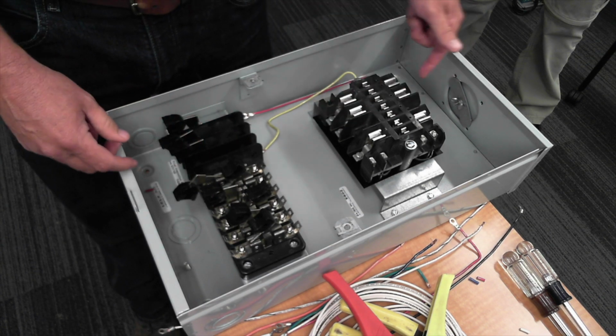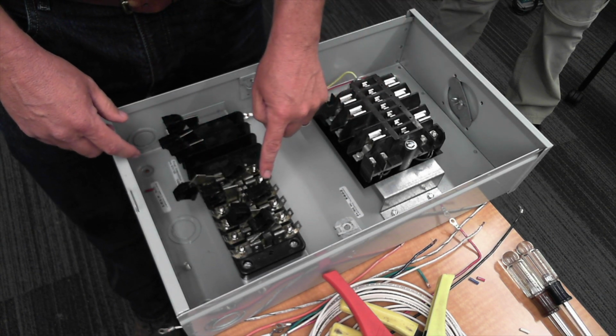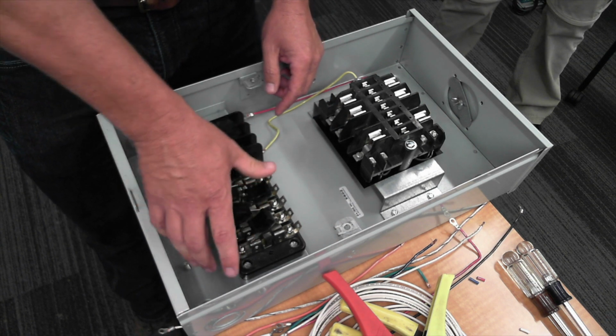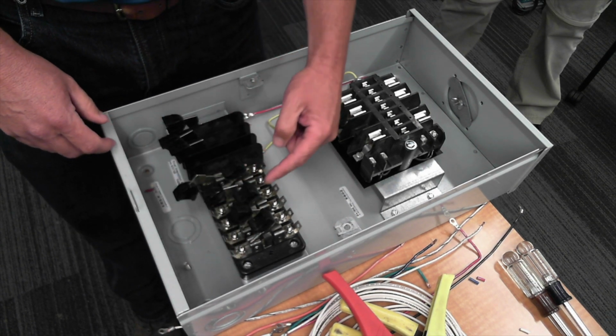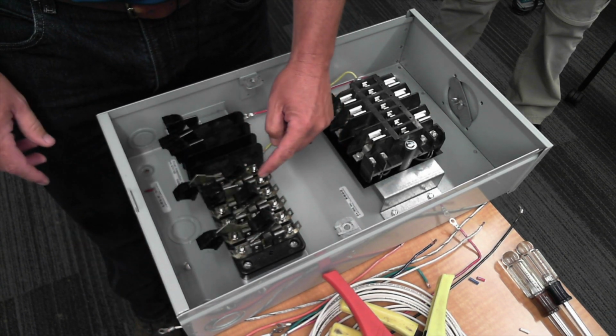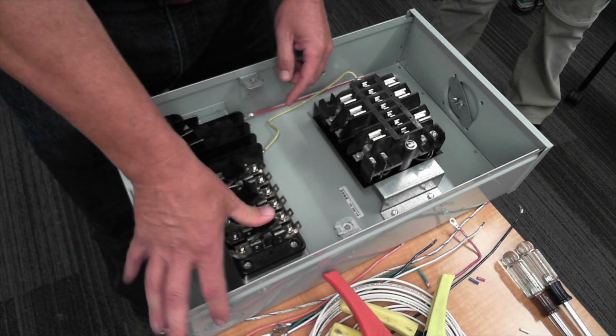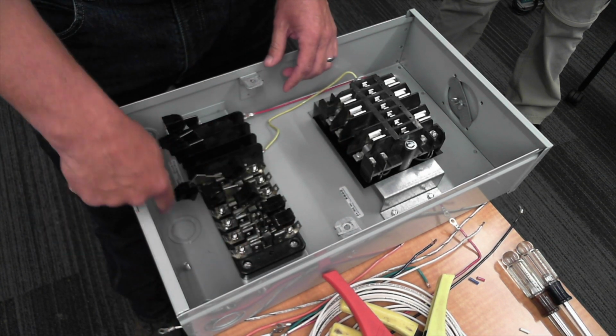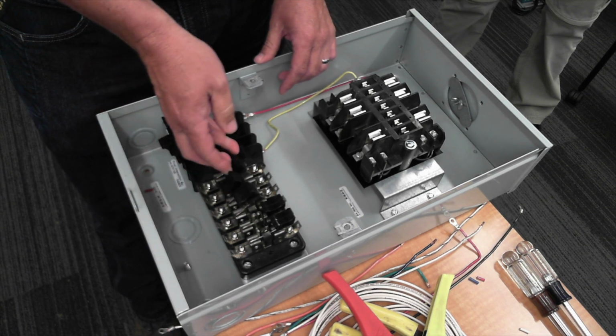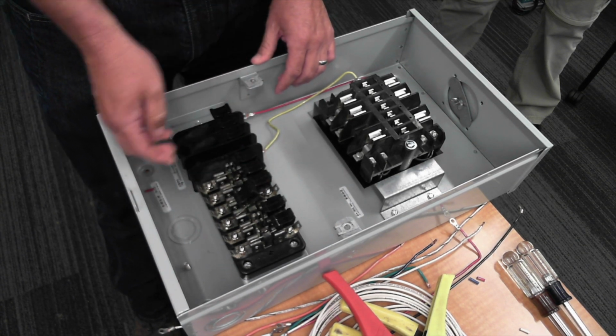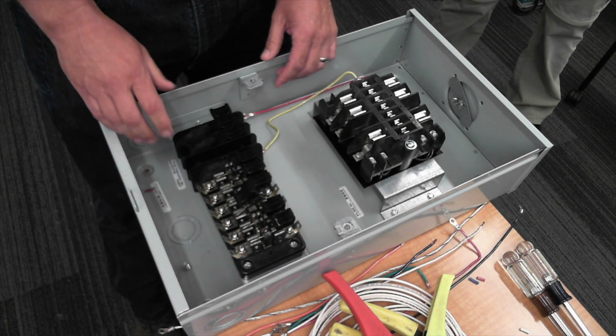So when you come down from the top side of the meter, you'll come down here for your potential. You'll see it all the way through - you'll have A, B, C returns, A, B, C potentials. Then you can come off the bottom side, that'll go to your CTs and your neutral. The bottom side here will go to the A, B, C voltage.